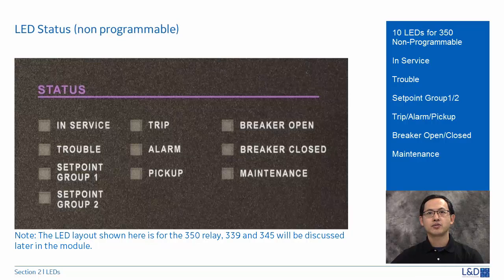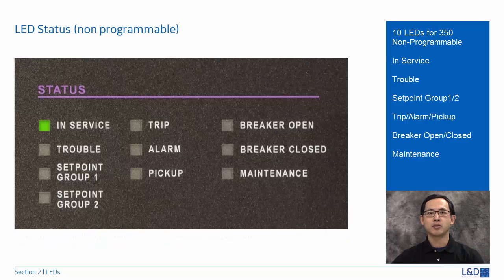In-service LED will turn on to green when the relay is set to ready in the setup menu and no major self-test error has been detected. Trouble LED will turn on to orange when the relay is not programmed or upon detecting a major self-test error.